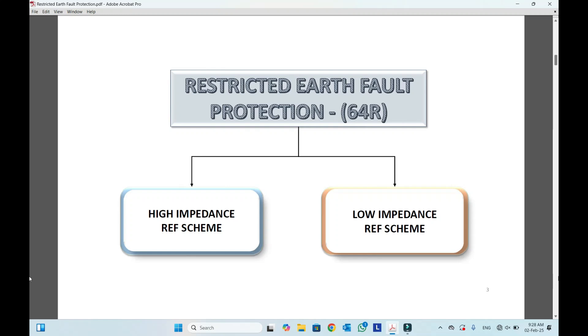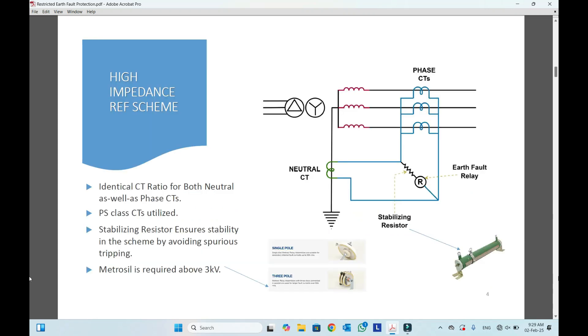Welcome back to Electrical Power Plus. In this video I will try to explain about restricted earth fault protection. The ANSI code for restricted earth fault protection is 64R. There are two types of REF protection: one is high impedance REF scheme and the other is low impedance REF scheme. In this video I will try to explain about the high impedance REF scheme first, how this scheme is built and how it will work.